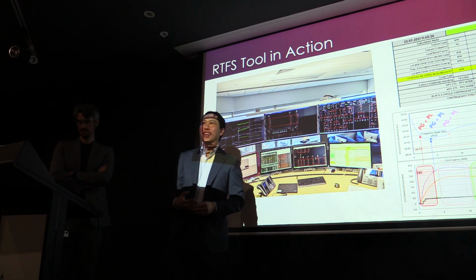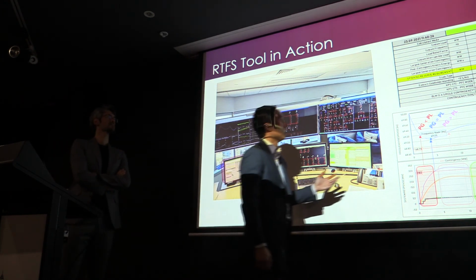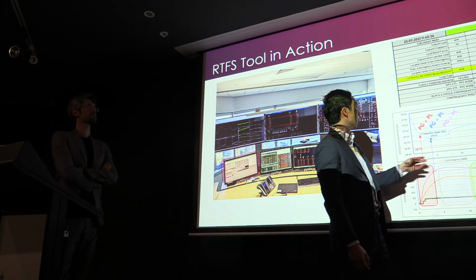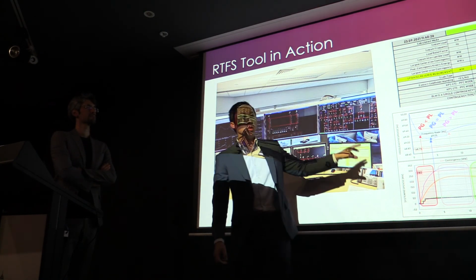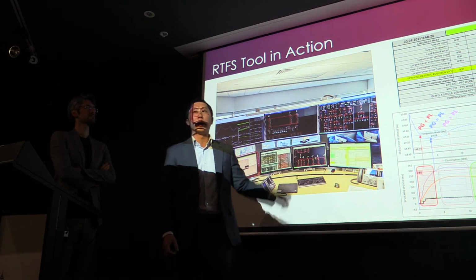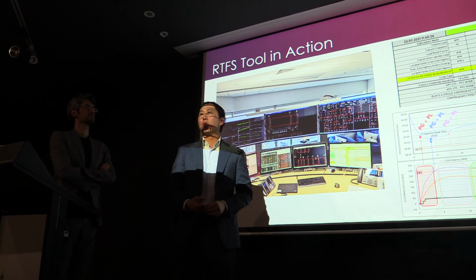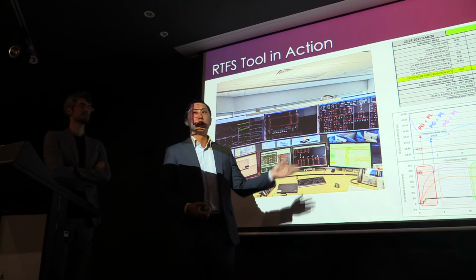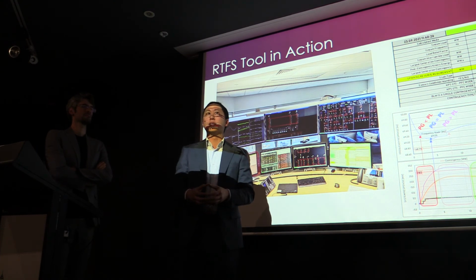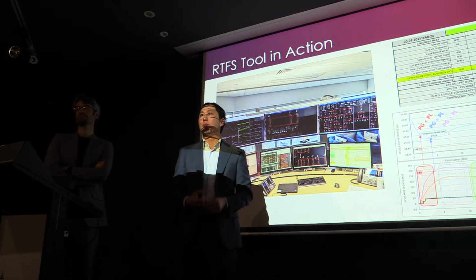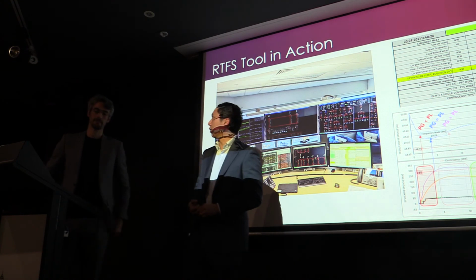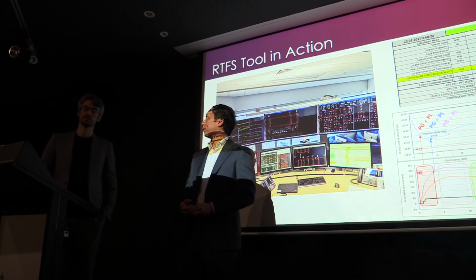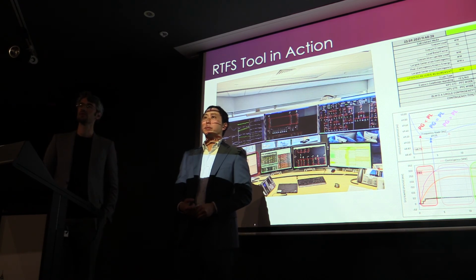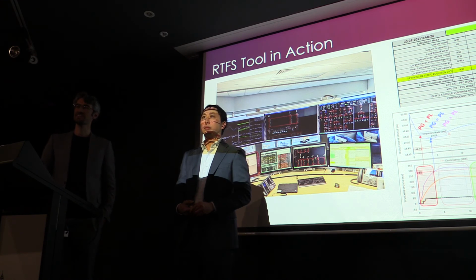No, they're all the same problem. In fact, we actually consider that, because Blue Waters here was only running at 197 megawatts, but you could see the continuous size was around 280. That includes over 80 megawatts of tripped solar PV that we're allowing for. We have a real-time measurement of how much DER is in the system, and we take a percentage of that as how much we think could trip off. That was actually calibrated on the event you're talking about. Was it the 1st of January or the 2nd? I can't remember. Yeah, the first, I think. I don't recall the date, but we did change the tool after that, so it's incorporated in there.